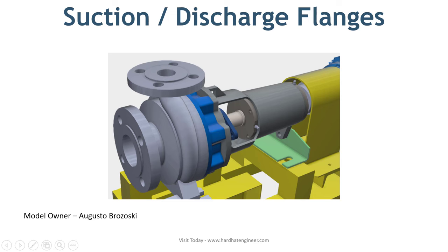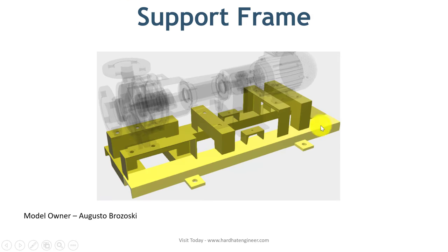The last part of the pump is the support frame. Pumps are mounted on a structural support frame. This frame provides the base for the pump and driver. Proper design is necessary to avoid vibration of the pump. For some engine-driven pumps, drivers are installed on a separate frame. The frame is constructed from I-beams and channels to provide strength.